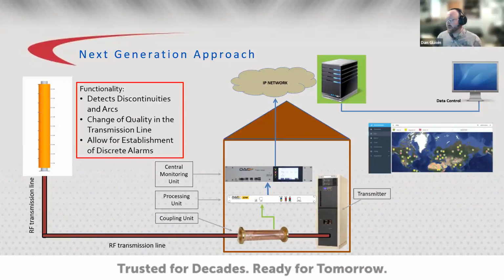The coupling unit is manufactured to the same transmission line size utilized after the transmitters or the coaxial switch to match the power handling capability of the unit to the overall system. The strategic placement of the coupling unit after the coaxial switch allows for the continuous monitoring of the system, whether or not it is in operation, so under full power conditions or completely dark. The results of these on and off air measurements can be very telling. It can identify temperature dependent mismatches by comparing measurements while the system is hot and after it's cooled down.